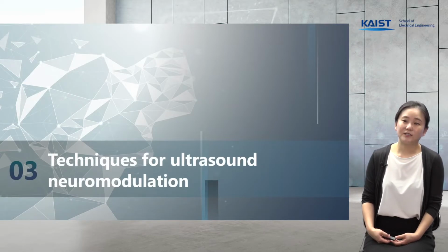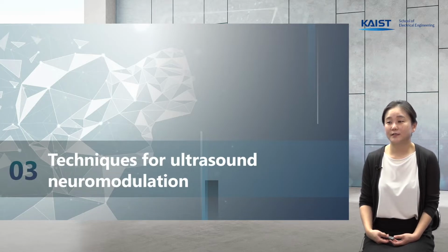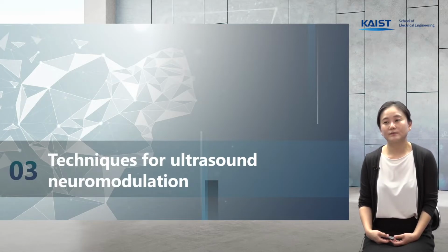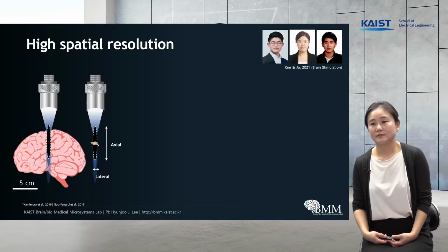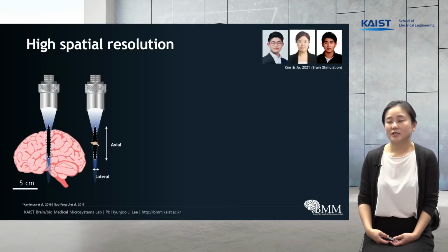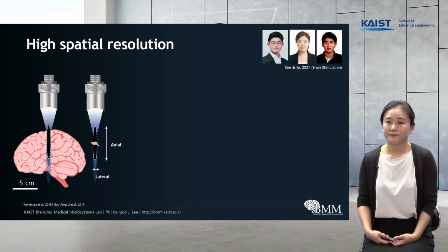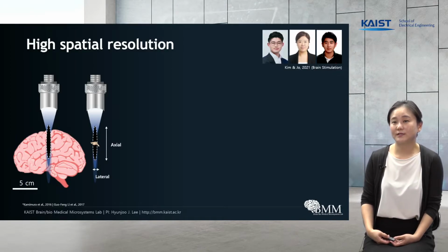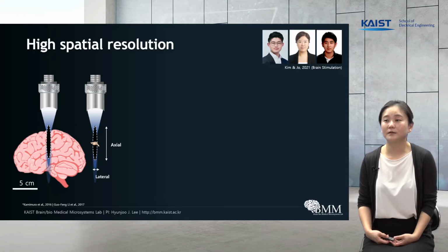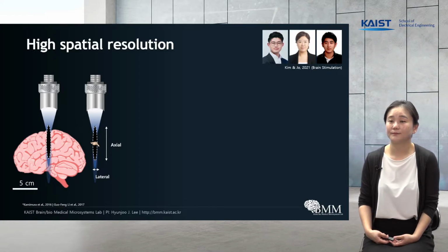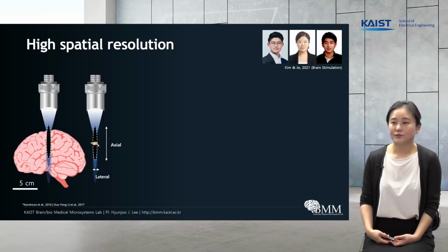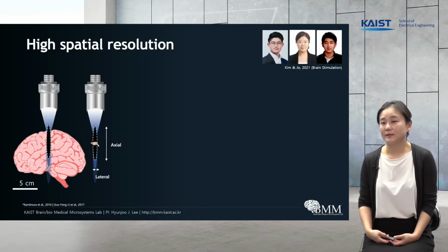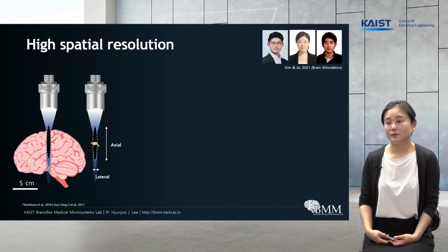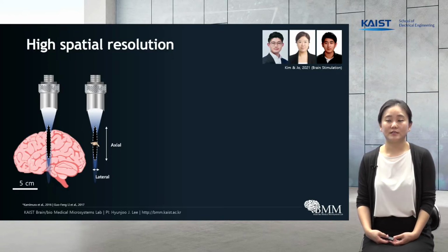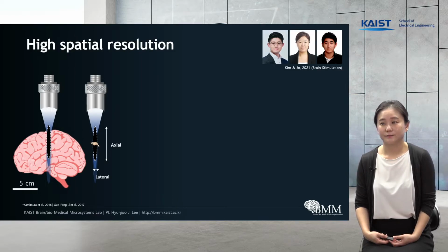Specifically, as engineers, we try to understand the current technical limitations and propose methods to overcome them. The device that generates ultrasound is called a transducer. The transducer used in a typical neuroscience lab is one of the simplest forms, a curved single transducer as shown here. For such a transducer, the curvature in the front focuses the beam. However, because we use only one transducer to focus the beam, as you can see from the figure, the focal spot is elongated in the axial direction.